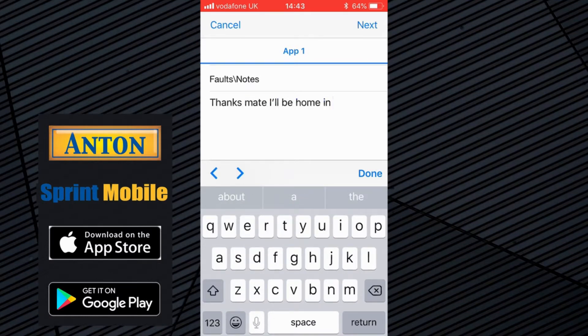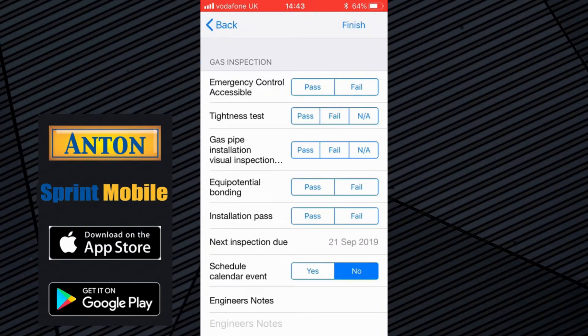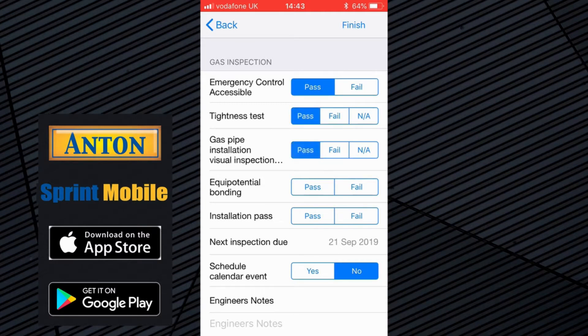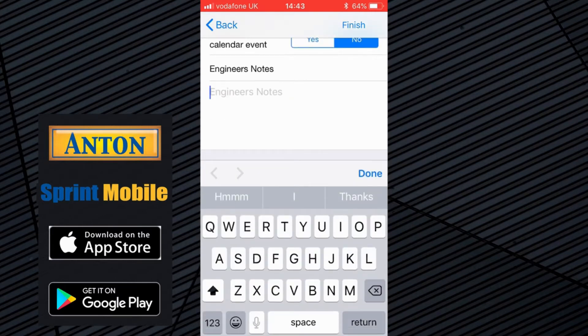Just put some text in there for the sake of it, and same with the remedial work — you can do the same. Then you've got the final page to finish this off. This was emergency control accessible and passed. Tightness test: if you've done a tightness test and linked it from those reports at the start, it would automatically pass or fail depending whether it was a passed or failed test. But let's say it passed. Next inspection due a year from today. Here you can schedule yes or no whether you want to put that into your calendar to remind you to get in touch with this customer to book another appointment for the annual service next year.